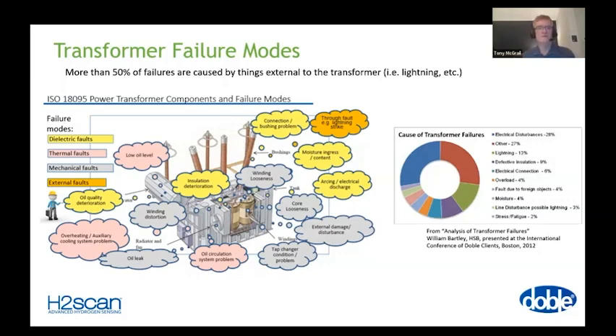So there are 4 different types of sources of failure on transformers, but we have to be careful because just looking at what failed doesn't necessarily tell us how or why it failed. On the right, we have some insurance company statistics showing that quite a lot of these sources of failure are outside the transformer — lightning, for example. It doesn't go into great detail, but the paper from Bill Bartley is useful, and if anyone's interested in a copy, let me know. The interesting thing is that different failure types are affected by how well the transformer has been kept, maintained, and looked after.